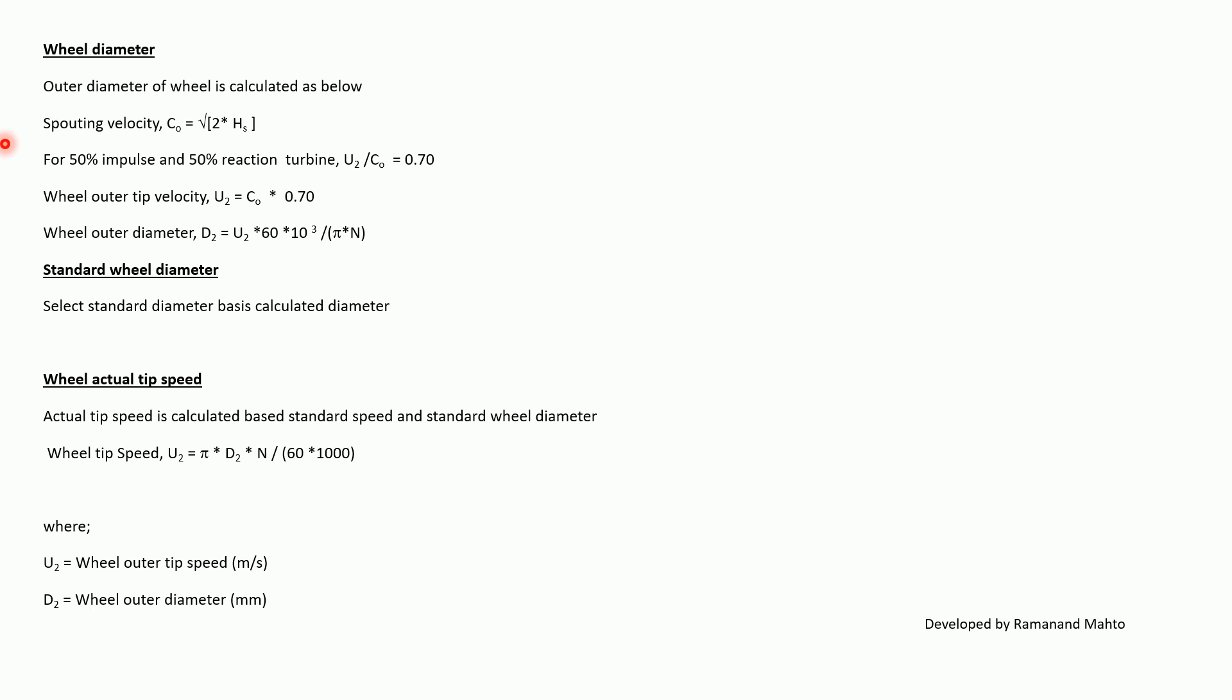Again, wheel outer diameter D_2 is equal to U_2 times 60 times 1000 upon pi times N. This way we can calculate wheel outer diameter. Now standard wheel diameter: select the standard wheel diameter based on calculated diameter.